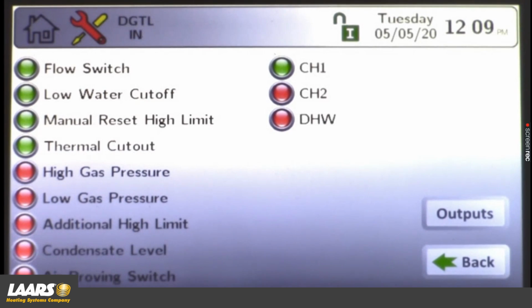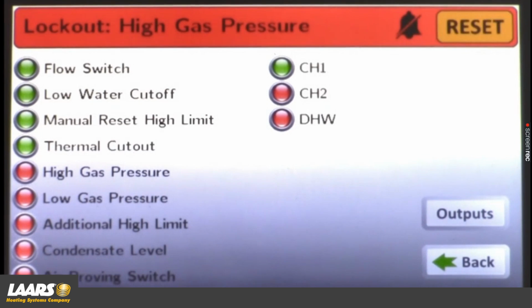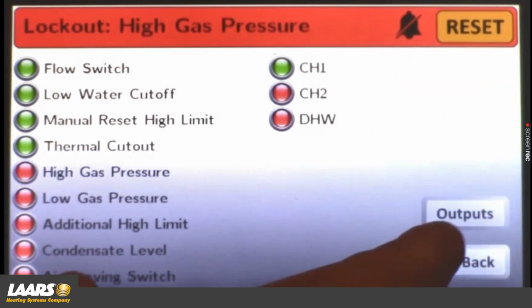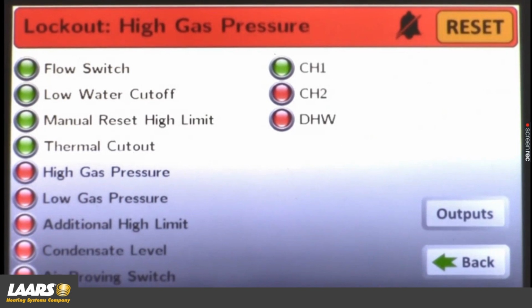So you'll see, up to the thermal cutout, if the boiler has it, it will read thermal cutout. Any device that has to be manually reset, such as a high gas or low gas pressure switch or low water cutout, you cannot just reset from the touchscreen display or the Laars Link display. You have to physically reset the device and then reset the control.